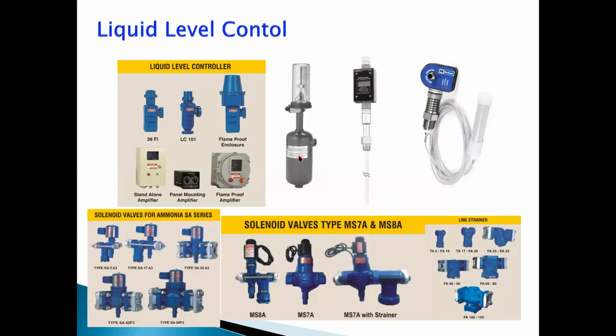Then we have mechanical float switches. In the construction of mechanical float switches, you have a ball and you have a magnetic switch. When the level goes up, the ball goes up and the magnetic switch operates, which gives you a changeover contact. You can have level transmitters, immersion types. You can have cable type transmitters.